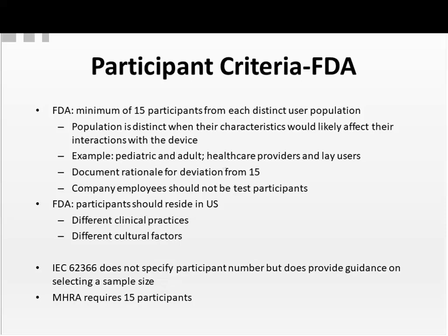Company employees should not be test participants. They know too much. Also, the FDA has said participants must reside in the United States. The reasons: there are different clinical practices and different cultural factors outside the United States that could make the results invalid.